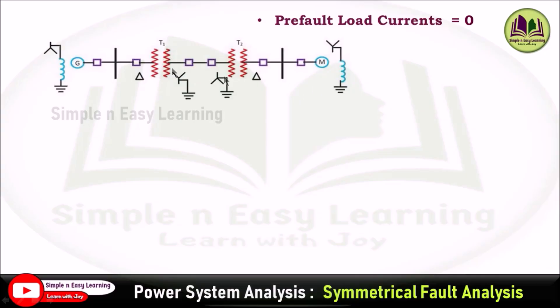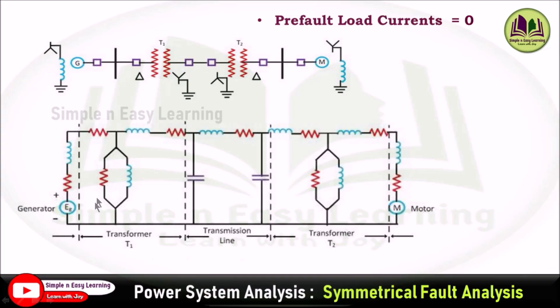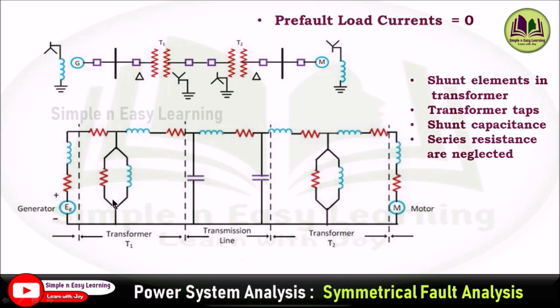Consider the single line diagram. If you draw an impedance diagram, it includes resistance, reactance, and capacitance. For generators there is resistance and reactance; for transformers there is a shunt component. These shunt elements in transformers are neglected, transformer tap settings are neglected, the shunt capacitances in the pi network of transmission lines are neglected, and all series resistances are neglected.